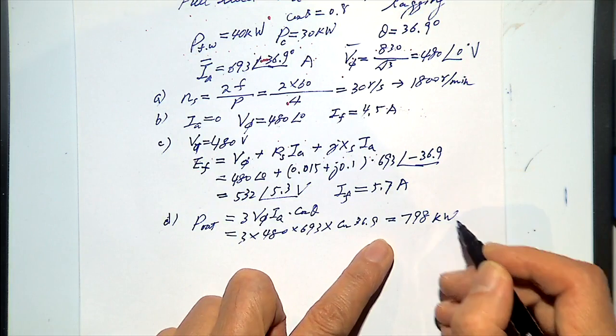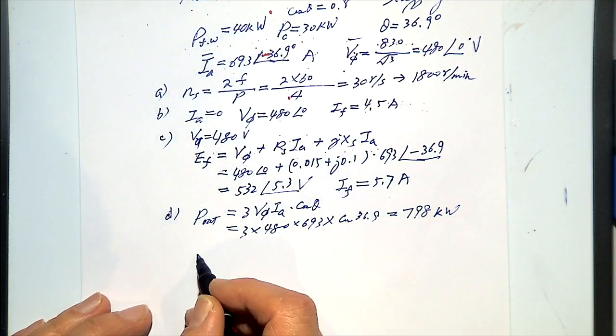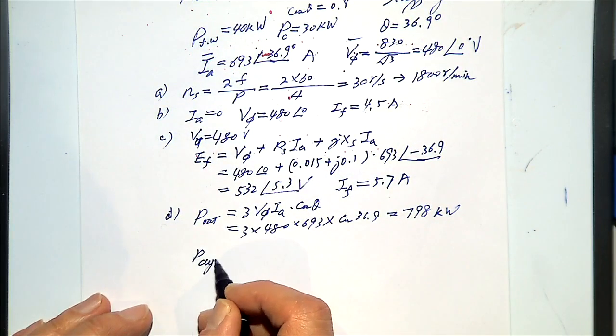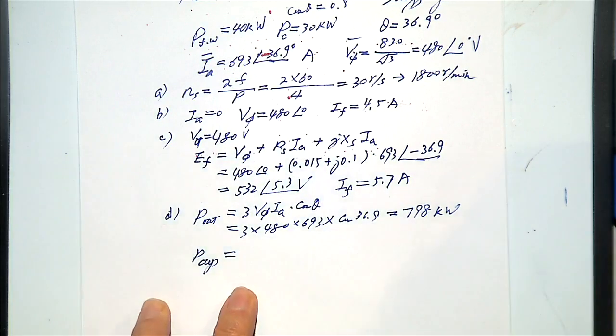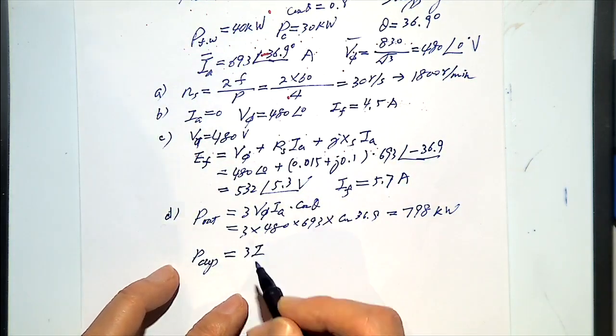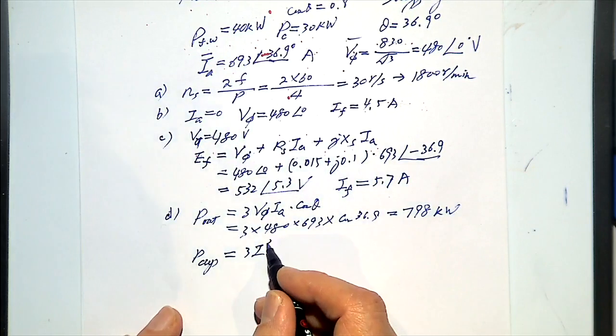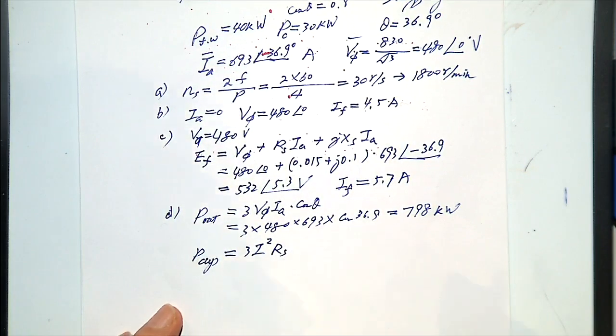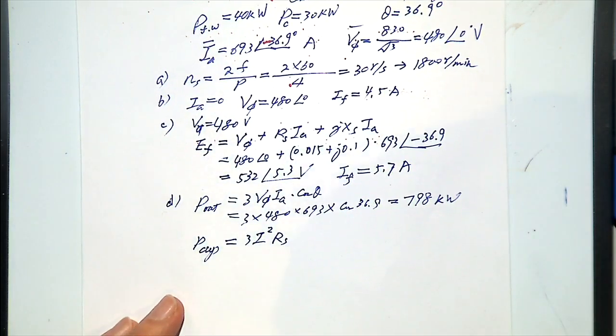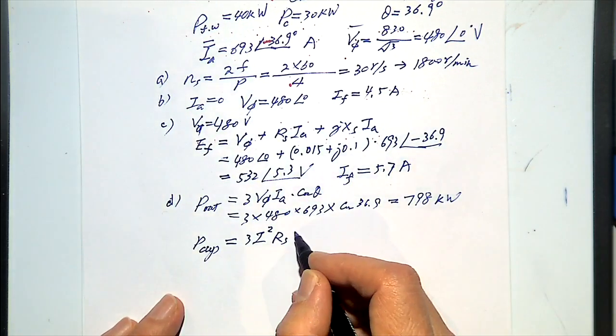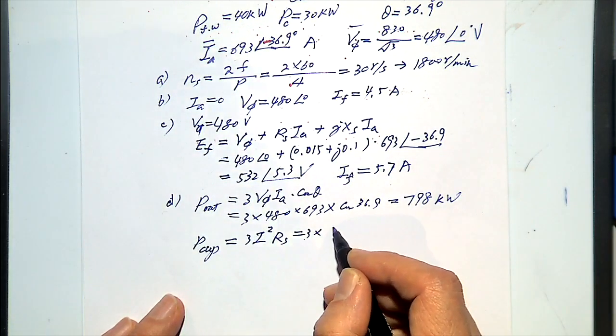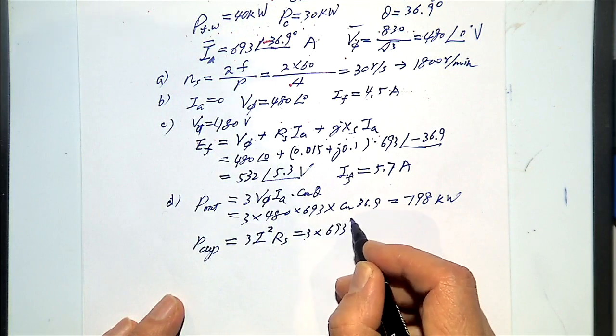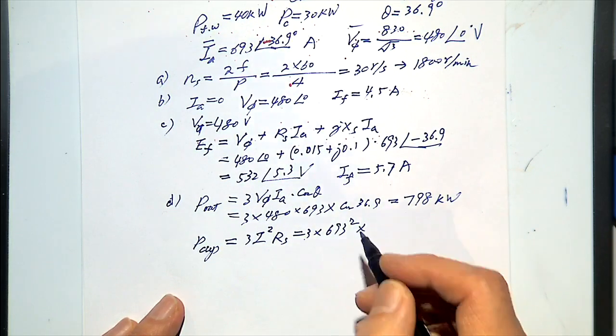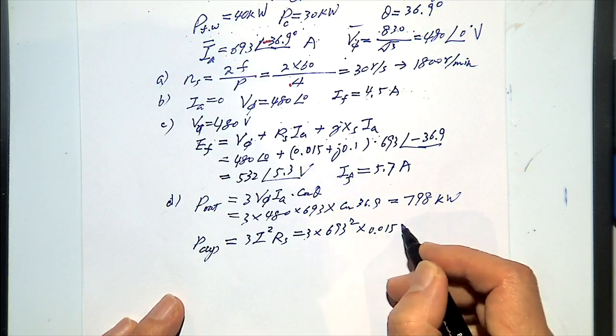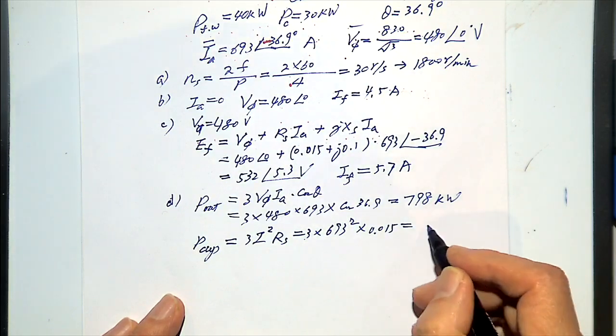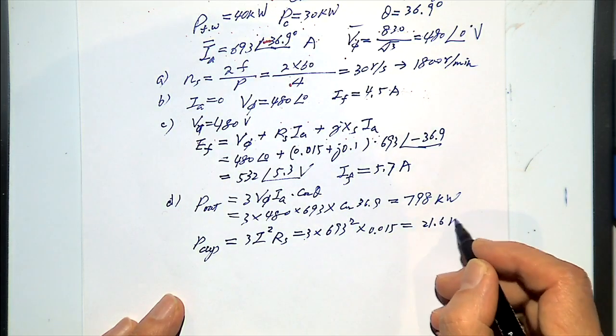You get 798 kilowatts. Then your copper losses are 3 times I squared times RS, where RS is your resistance. That's 3 times 693 squared times 0.015, giving copper losses of 21.6 kilowatts.